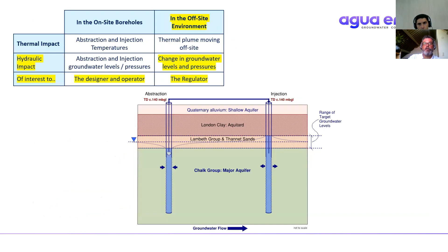I've talked about the range of target groundwater levels already, that we have to try and maintain within a certain unit. A question often asked at the feasibility study or even detailed design stage is: what's the minimum distance between your boreholes? Well, it depends how big your site is, how much flow is required, what the thermal imbalance is, and what the groundwater flow mechanisms are - including what the groundwater through flow is, and the hydraulic gradient through your site.